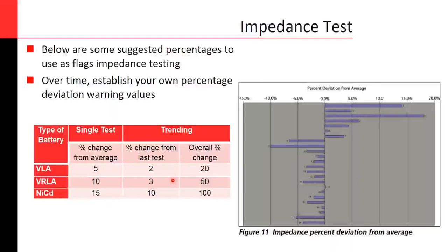If you have a previous test, you are looking for a change not higher than 2%. And if you have already established a baseline value, you are looking for a change not higher than 20% from that baseline value. And here in this slide, you can see the result for each cell graphed in percentage, graphing the change in percentage from the average.